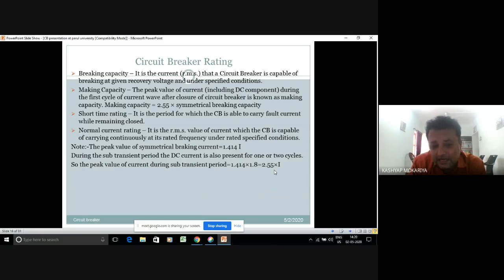But once it is hitting that subtransient phenomenon, at that time the current is very high and the reactance is low, it is vice versa. Like the subtransient reactance is low, then the transient one, and then the steady state. So you have to design your breaker according to your subtransient state, and that I have covered in the presentation, how to take care of that.